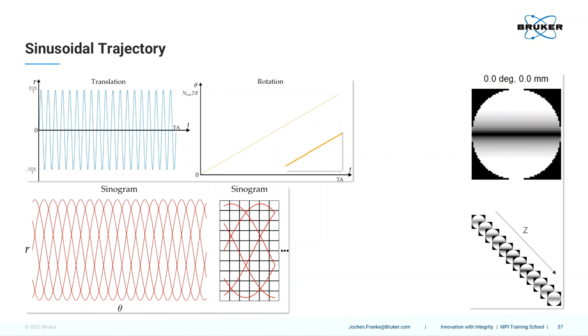Now what we are doing is we translate our field-free line and continuously rotate, so as to minimize the inertia of the system. If you zoom in, it's just a straight line. So now sampling of the sinogram is no longer a meander curve. It's a sine pattern, and now we need to discretize and fill the sinogram accordingly.